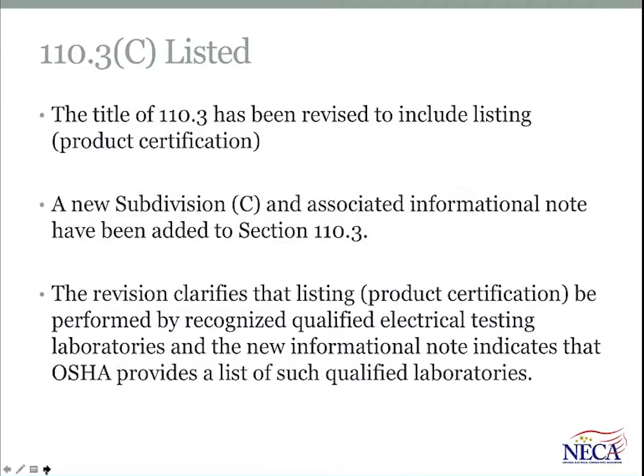So staying with the approval process, Article 110, specifically 110.3, has been modified to include a new subdivision C dealing with listed and product certification. The title of 110.3 in general includes the words product certification, and the new subdivision C gives an indication to users of the code what listed actually means. And it means testing and evaluation by a qualified electrical testing laboratory that's set up to perform such evaluations for acceptability in the field.